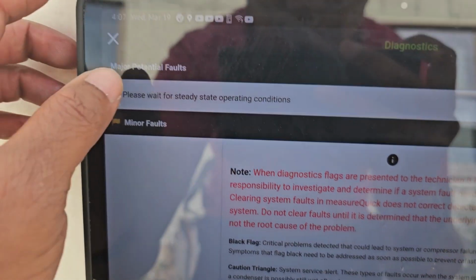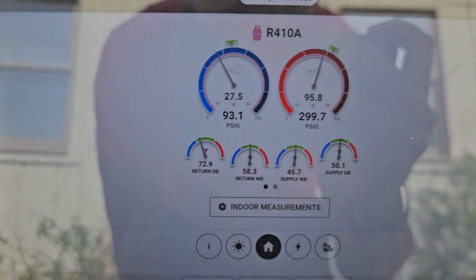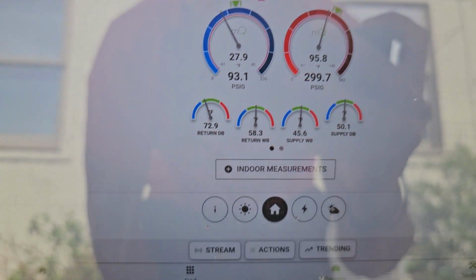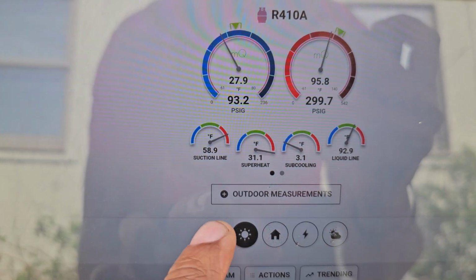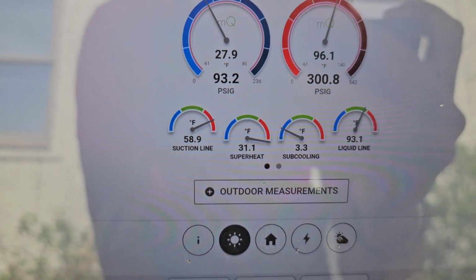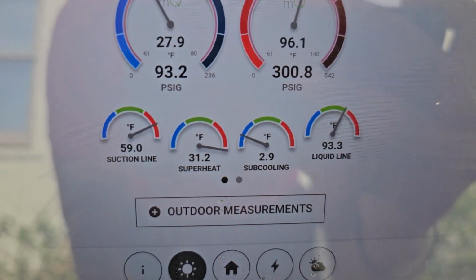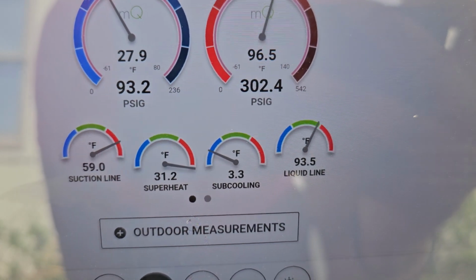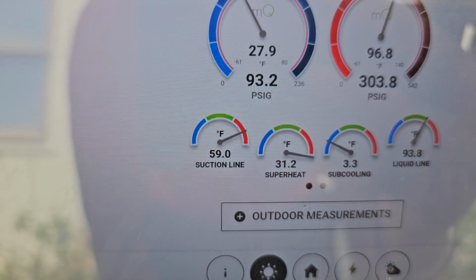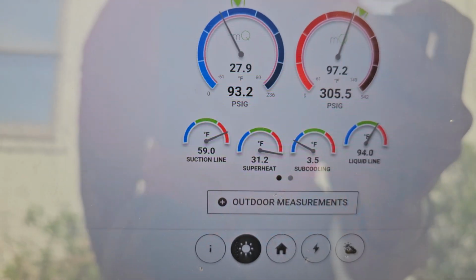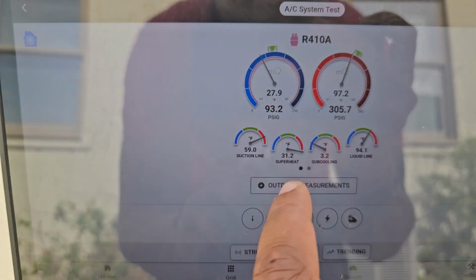Is this already saying we've got issues? No, okay, it's still saying wait. Just based off of this stuff, guys, what do you think is going on here? Really high superheat, low subcooling, suction line's pretty warm.